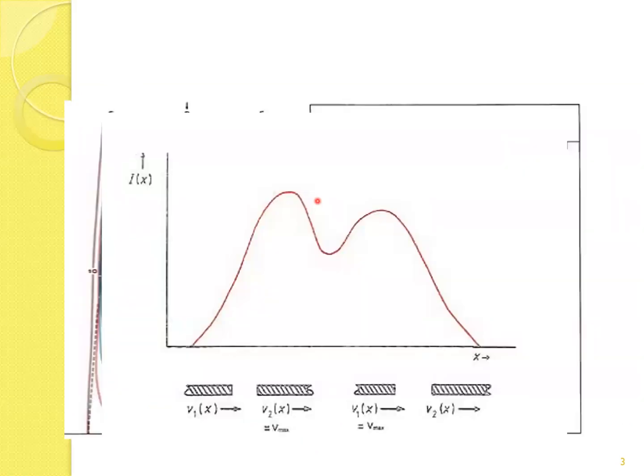But if you use MLCs, which are two dimensional, and at that moment two banks move, like A bank and B bank in MLC. One is a forward direction, another is a reverse direction, and it can generate a modulated profile according to your requirement.